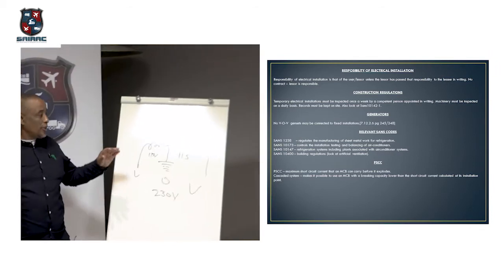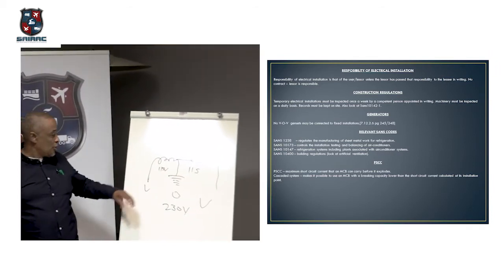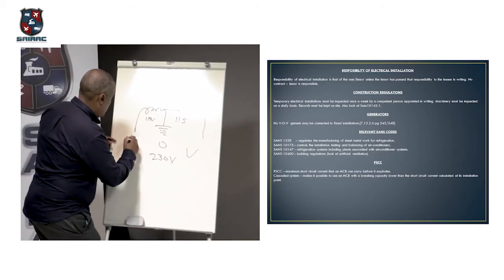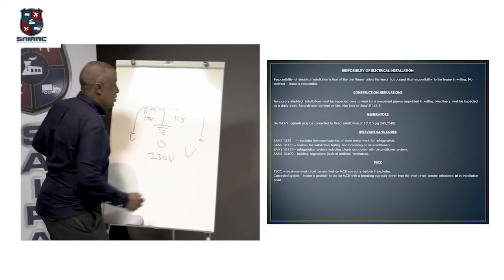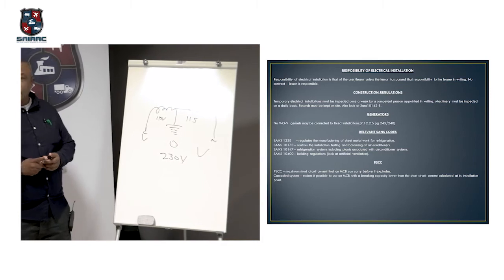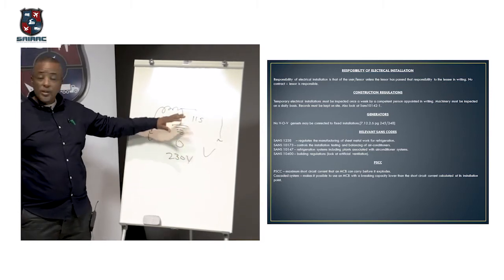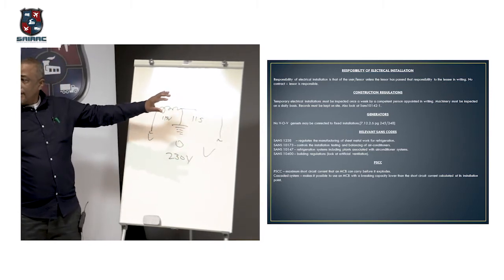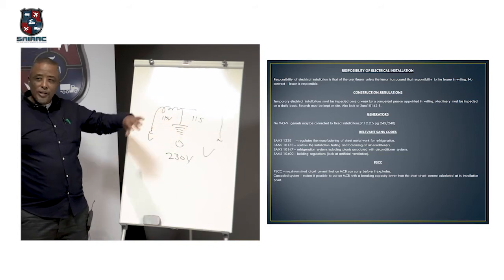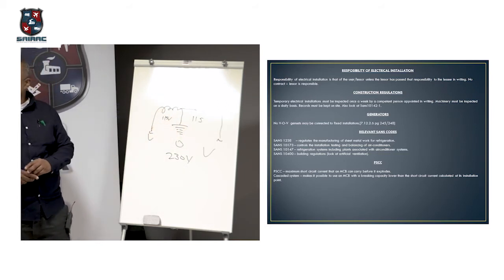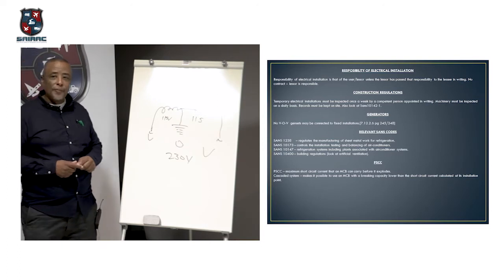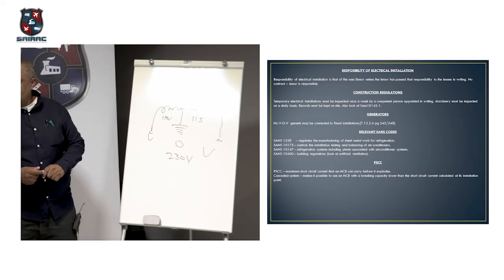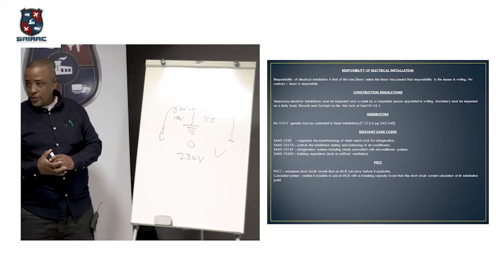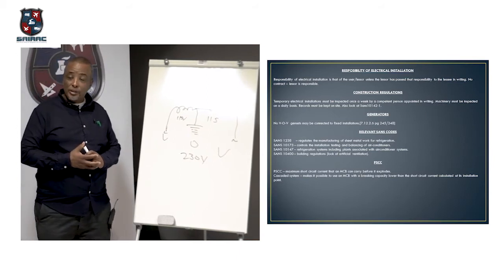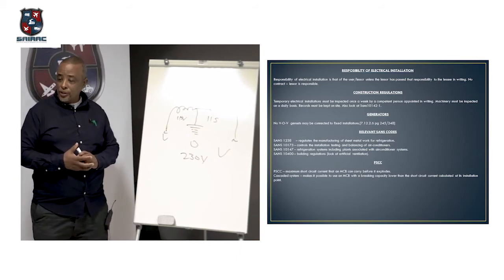Okay. Talking about your elevated voltage between, let's say that's your live, that's your neutral. You elevate it between neutral and earth if you have to test an insulation, and your voltage is slightly elevated, whether it's an appliance, particularly fridges, deep freezers and stuff. Deep freezers, more likely, because deep freezers don't have to be on earth leakage, except on events.